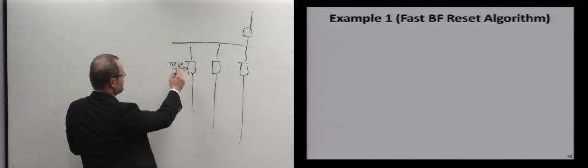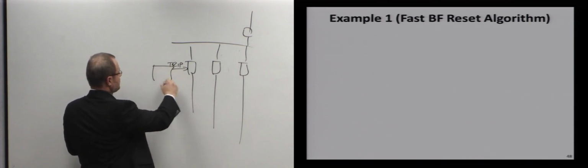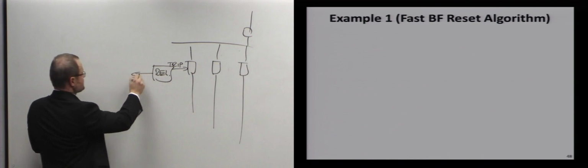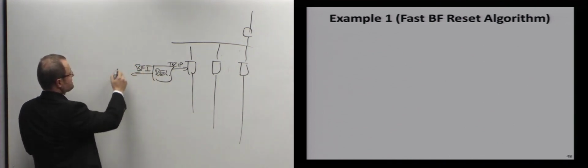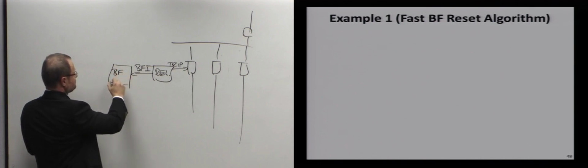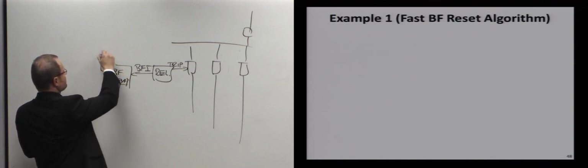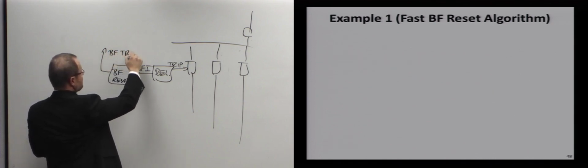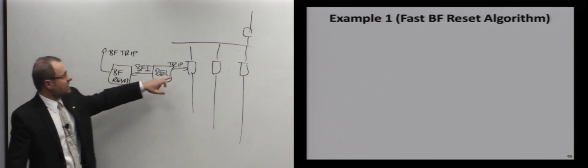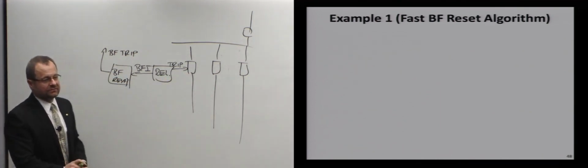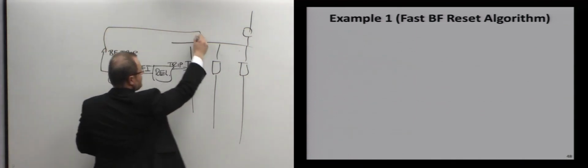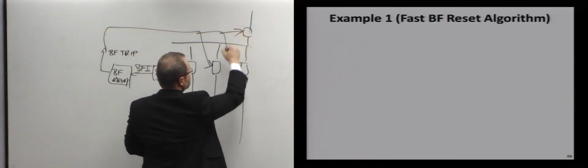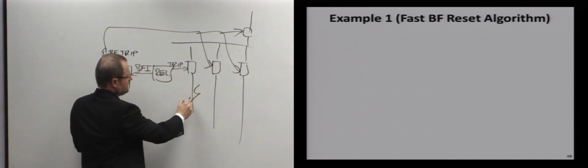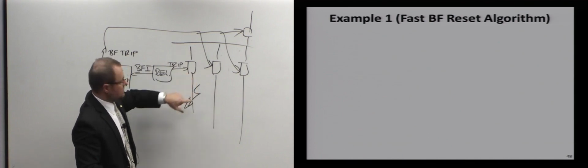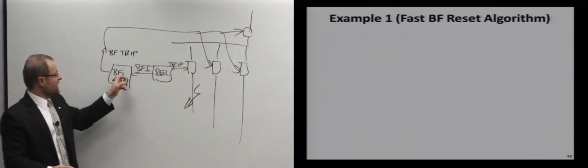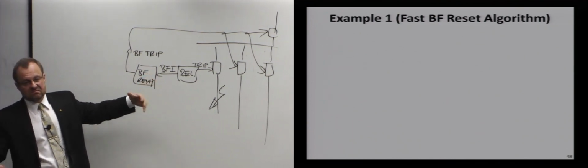Now, if the relay that trips initiates breaker fail, so there is a breaker fail initiate signal to a breaker fail relay, and that breaker fail relay says breaker fail trip, meaning that yes, I detected that this breaker didn't really open. What do we do? We take that signal and we have to do this. We have to trip all those guys, because that's the only way to cut the flow of current towards that fault. So if breaker fail relay misoperates, we just made a big hole in the power system.